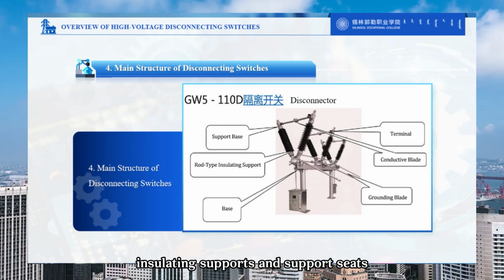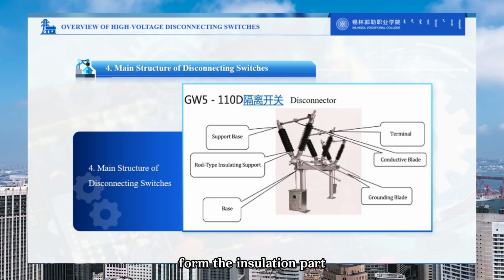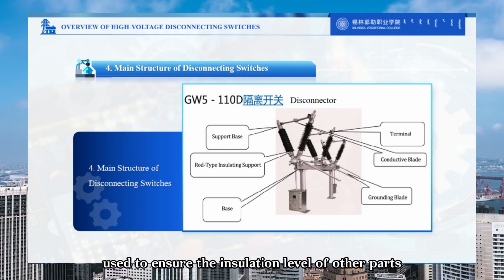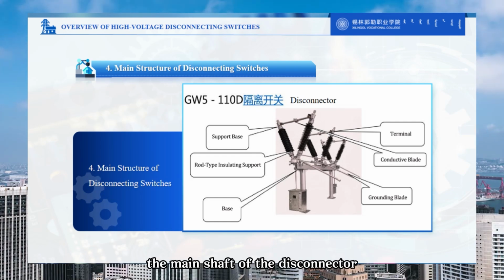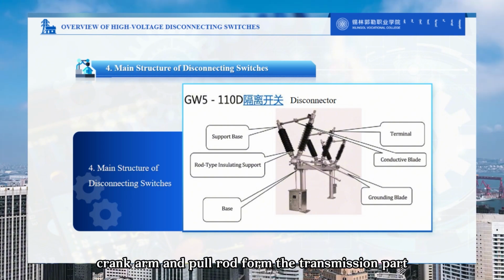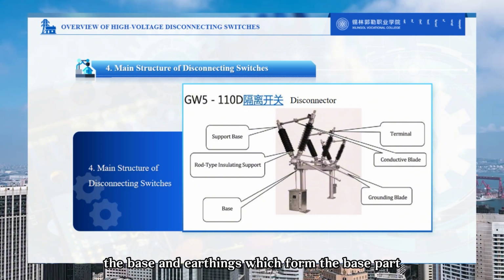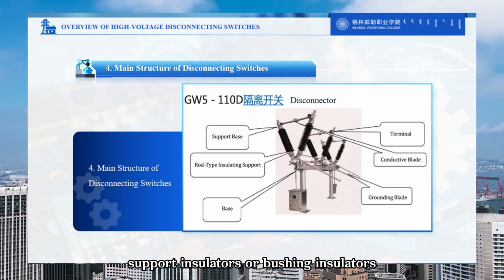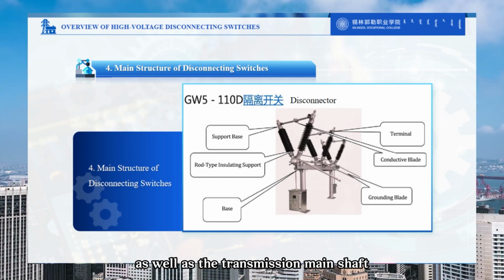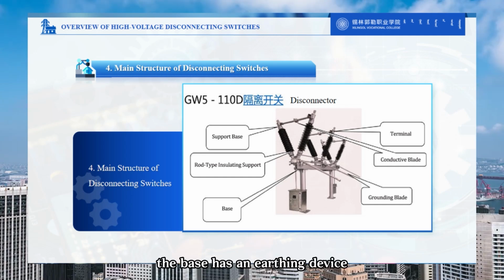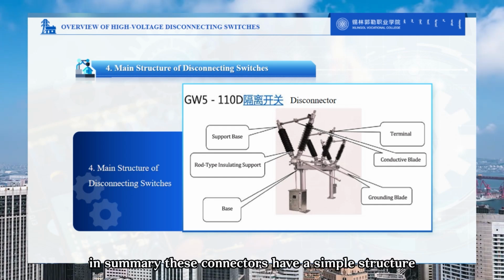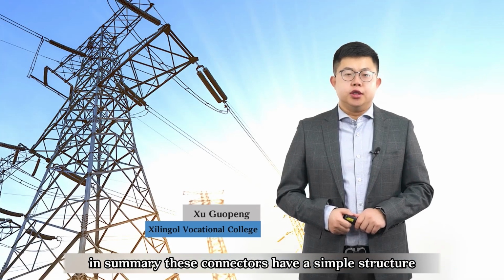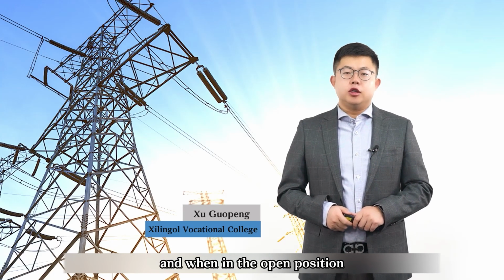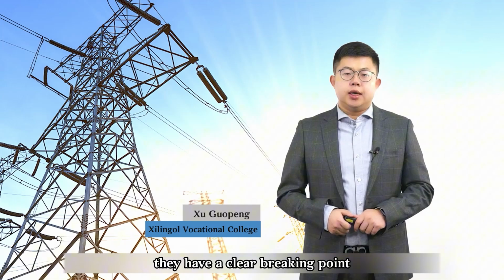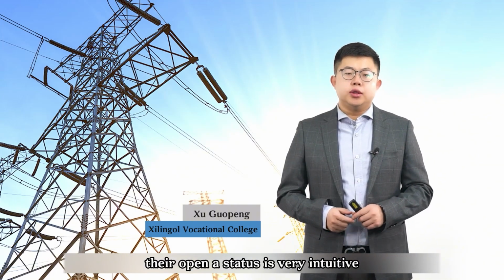Rod-type insulating supports, and support seats form the insulation part, used to ensure the insulation level of other parts. The main shaft of the disconnector, crank arm, and pull rod form the transmission part. The base and earthing switch form the base part. Support insulators or bushing insulators, as well as the transmission main shaft, are fixed on the base. The base has an earthing device. In summary, disconnectors have a simple structure, no arc extinguishing device, and when in the open position, they have a clear breaking point. Their open status is very intuitive.